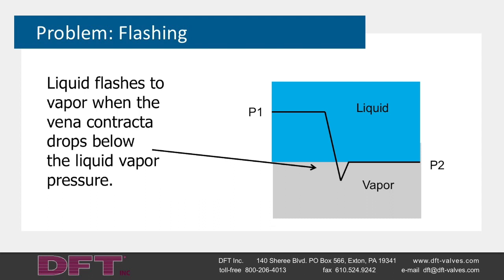Problem: flashing. Flashing is a liquid flow phenomenon that occurs when the pressure in the liquid flow stream drops below the vapor pressure of the liquid. When this occurs, vapor bubbles form in the liquid. This condition will typically occur at the point in the flow stream where the flow area is at a minimum, the velocity is at a maximum, and the associated pressure is at a minimum.